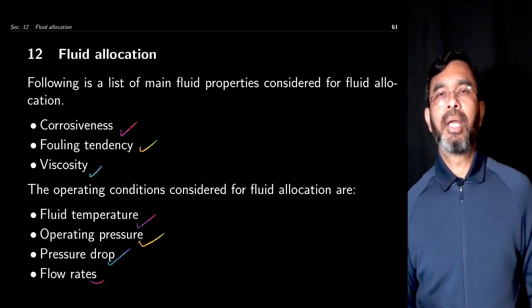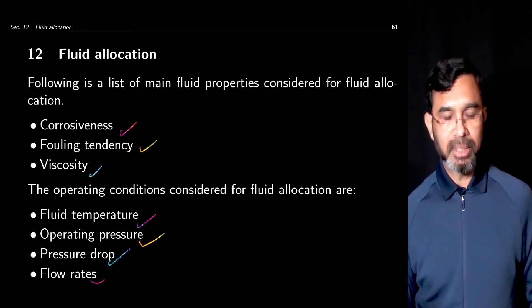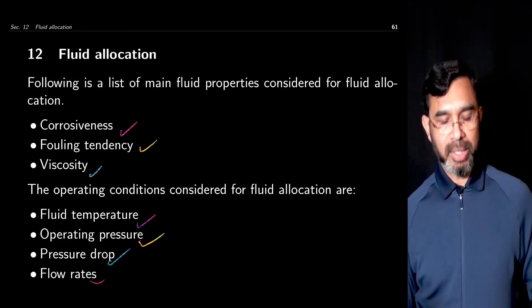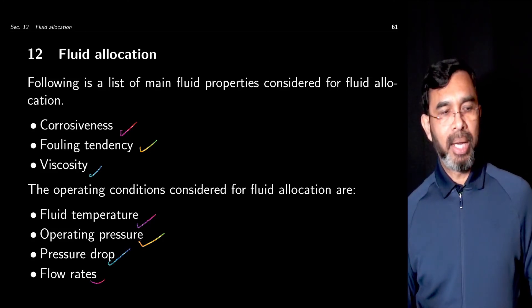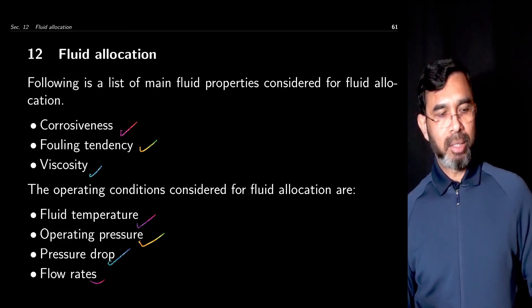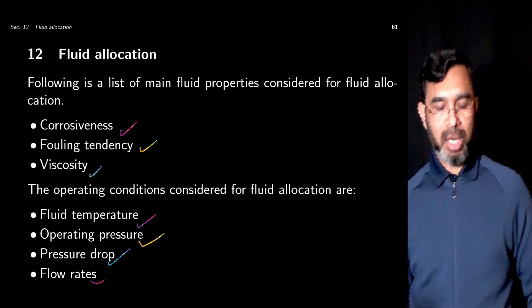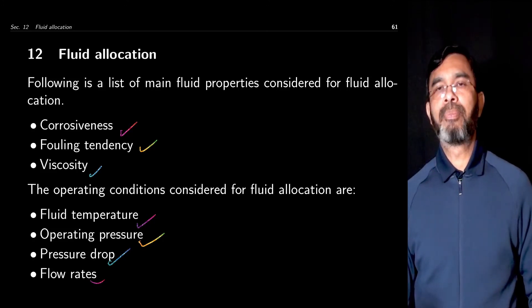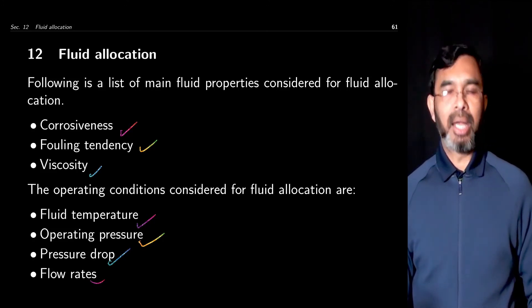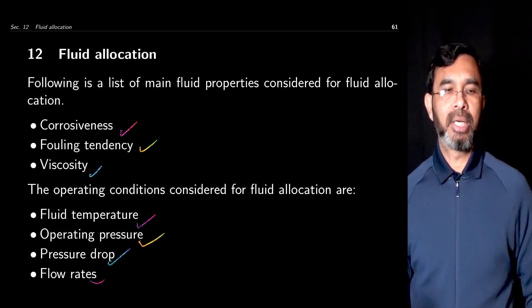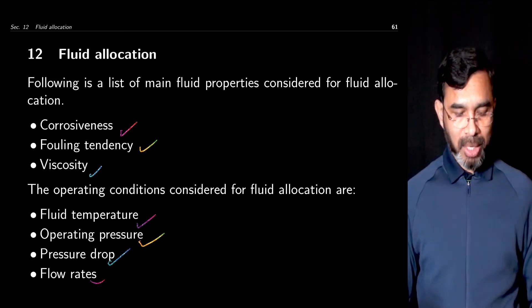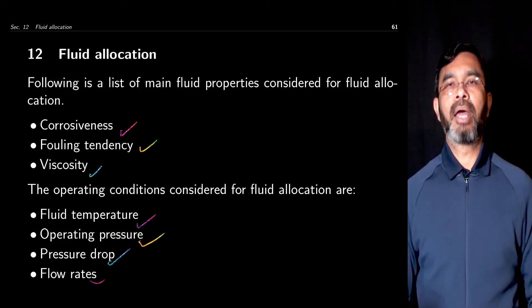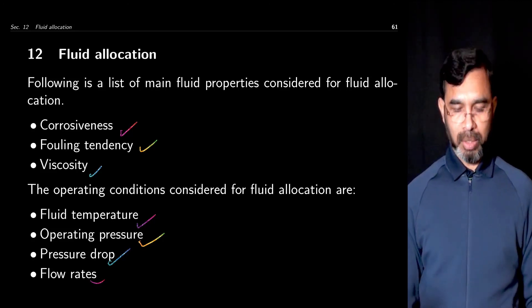In summary, the corrosive fluid goes to the tube side, the fluid having a fouling tendency goes to the tube side. For viscous fluid, depending on flow conditions, it can go to either the tube side or the shell side. For high temperature fluid it typically goes to the tube side. If the fluid is at high pressure or the allowable pressure drop is low, it goes to the tube side, and fluid with the higher flow rate also goes to the tube side.